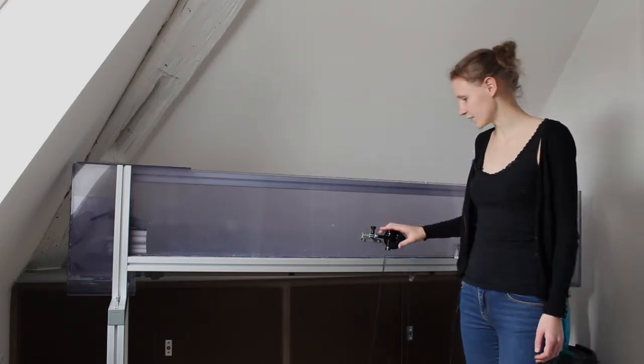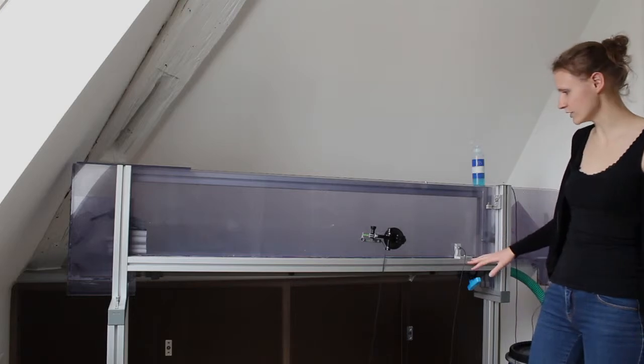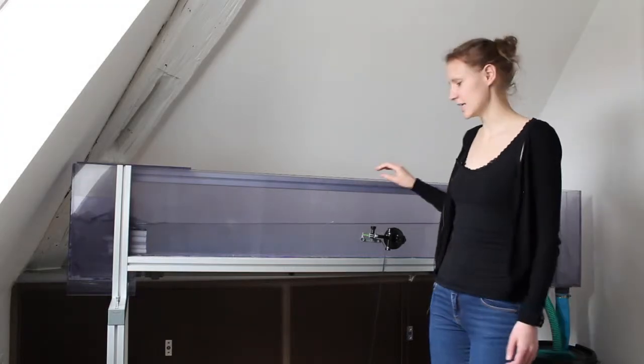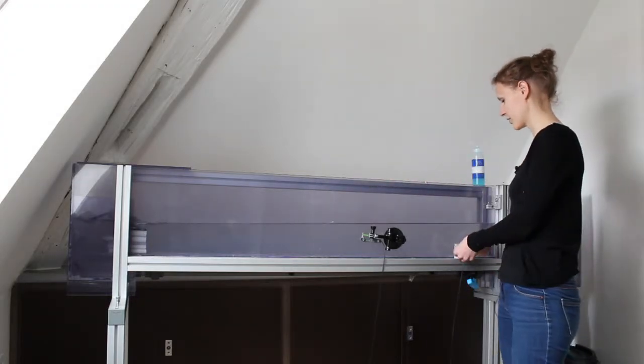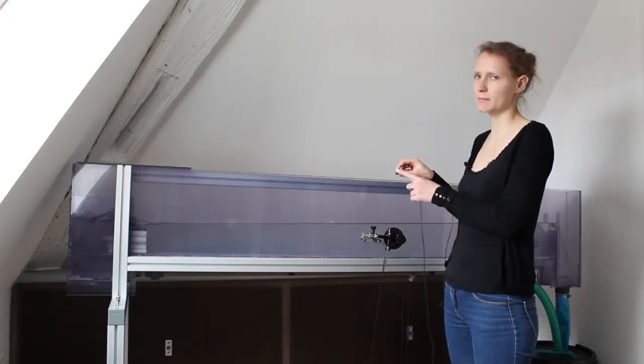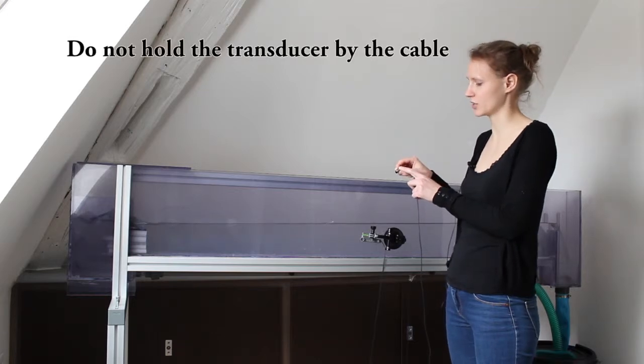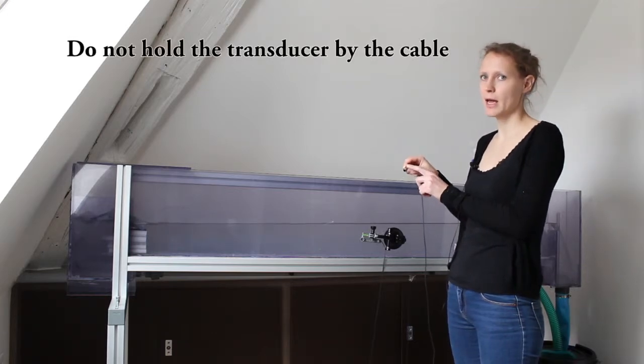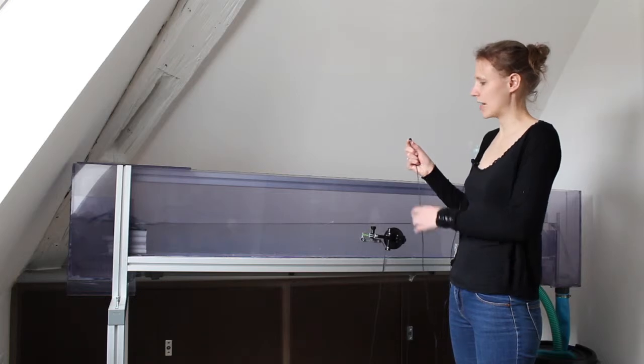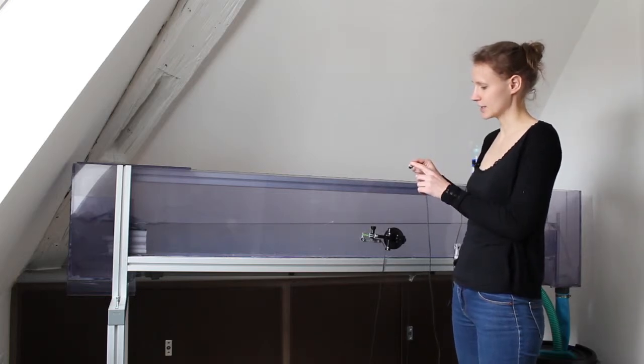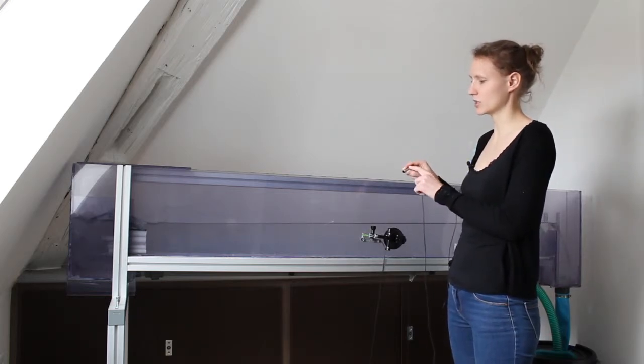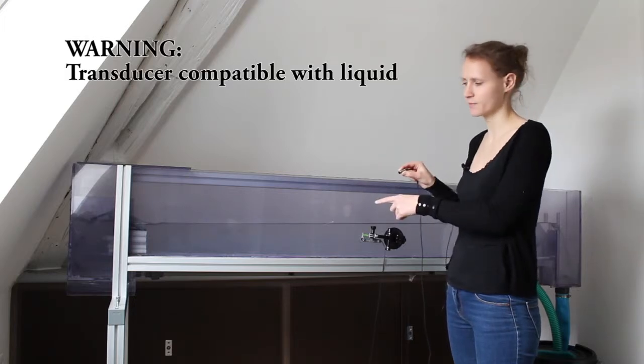I have here several transducers and several holders. And I will now turn the pump on. The first idea is to put your transducer directly in your liquid. You can first hold it manually. Hold it by the head, not by the cable, as the junction between the head and the cable may be damaged. You will have to pay attention that the material of your transducer is compatible with your liquid.